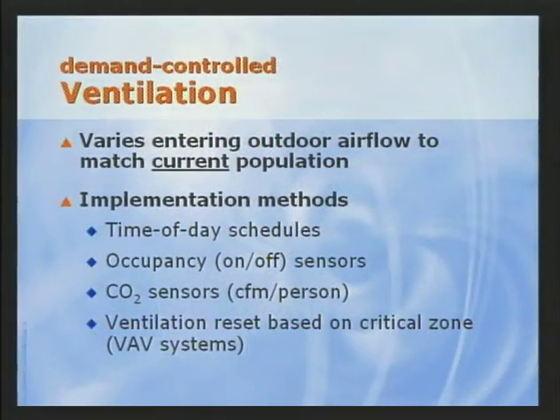This has led to the development of a number of different control strategies to minimize the amount of outdoor air used. The goal of all of these strategies is to vary the amount of outdoor air brought into a space to match the number of people currently in the space. Some simply use an occupancy sensor or a predetermined schedule to turn off ventilation when no one is in the room. Others, such as CO2-based systems, attempt to count people or determine current CFM per person by sensing how much exhaled carbon dioxide is in the space.